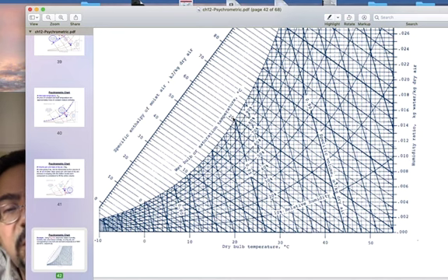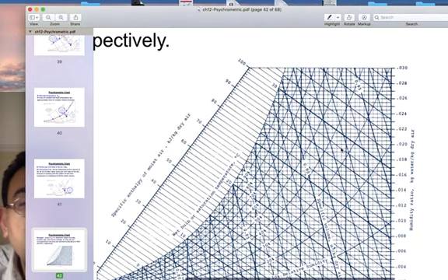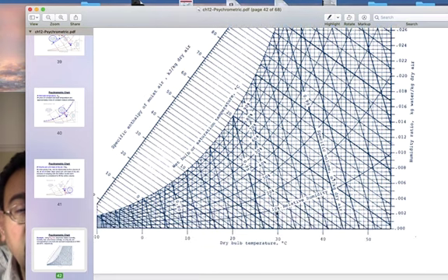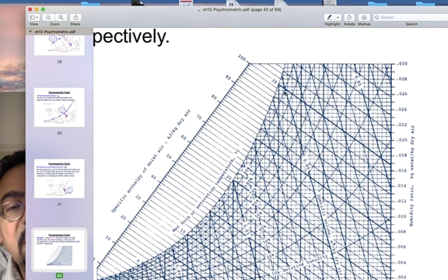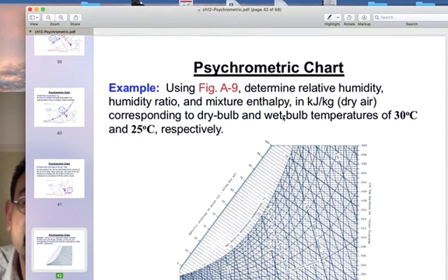Well, it's written 20, but also when you follow that line down there, it's 20. That line is a wet bulb temperature of 10. You go up at the end and you go down, it's 10, and so on and so forth. Why is that? Because for each one of those lines, that's 30 wet bulb temperature. I bet if we go all the way down, we will end up hitting 30. Clear? Because at 100%, the wet and the dry become the same.